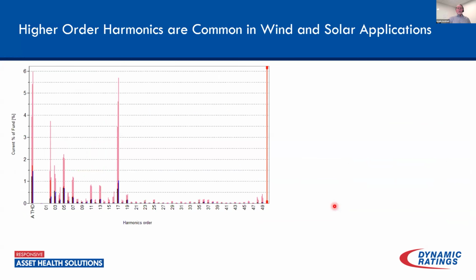So again, anytime we've got harmonics on that system, that can introduce additional aging on our insulation. Now, one thing I talked about, like I said, early in my career, we always focused on what they called the triplen harmonics, the thirds, the ninths, those types of things. And when there were a lot of 6-pulse drives out there, we saw a lot of 5th and 7th harmonics associated with that.